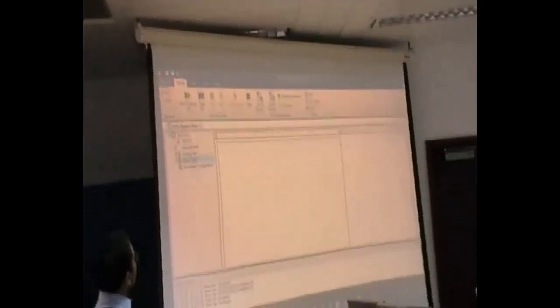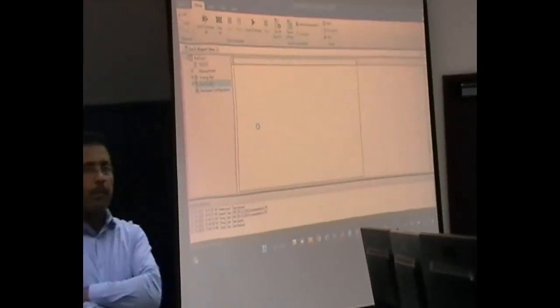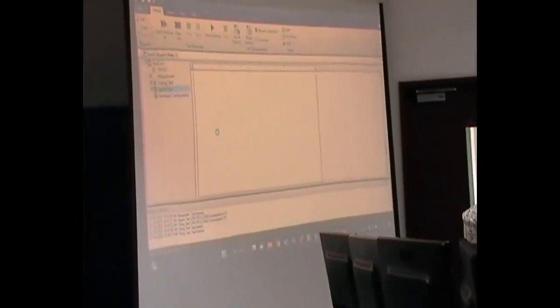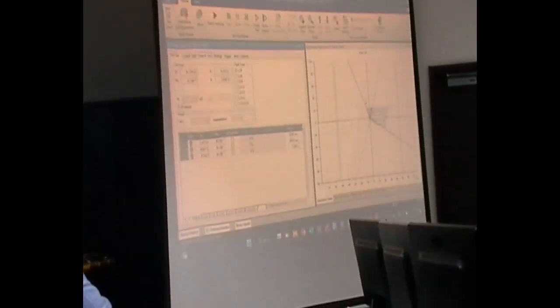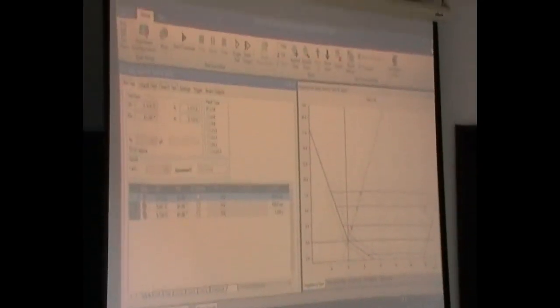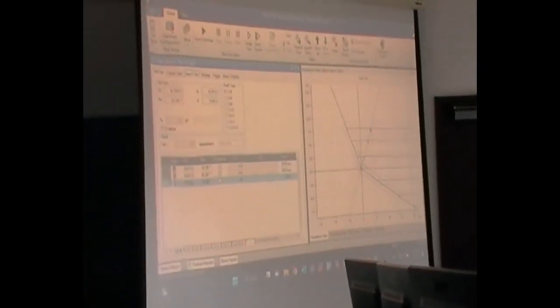Last test. Here all I want is to make sure that it's sensitive enough. My setting is at this particular line, but the relay maybe goes a little bit higher or lower in terms of impedance. So I'll do this test and I will test the reactance and the resistance.